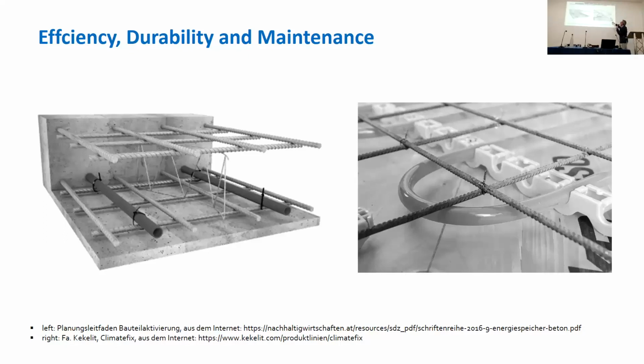The other says, get it down even lower than the steel, very close to the surface. And this one says it's good for demolition because it's more risky to be demolished. But if it is, you can repair it. In this case, it's very tricky to repair these pipes. If you find a guy with a big drill and he drills a hole into it, it's very tricky to get this fixed, because the static guys, the construction guys, do not like you to cut their steel. They say the steel is important, more important than your pipe. And if you try to fix it without cutting the steel, then it's really, really a thing. So I'm more fond already of these systems because I really can fix them.